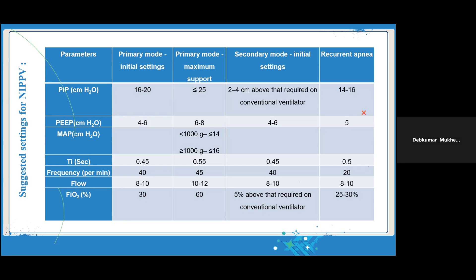As a secondary mode, initially, whatever PIP you have set, you can go 2 to 4 centimeters higher. That was on the conventional ventilator. If the baby is on conventional mechanical ventilation, PEEP 4 to 6, Ti 0.45, the rest of the things are the same. And FiO2 5% above that required on the conventional ventilator. If there is recurrent apnea, then you have to set PIP on the lower side, like 14 to 16, PEEP 5.